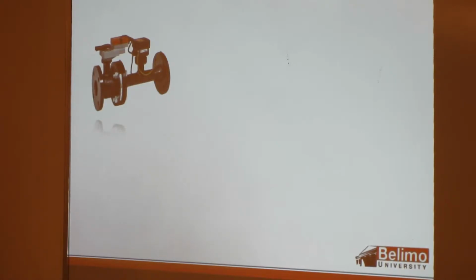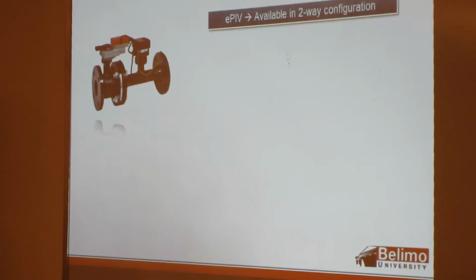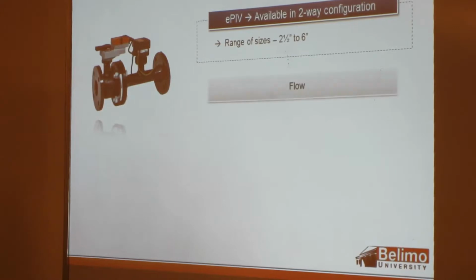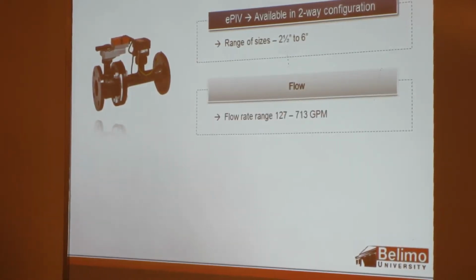Electronic pressure independent valve. We're achieving the same results in a little different manner here. It's available in two-way configuration, just like PICCV. Like I said, all PI valves are going to be two-way. This 2.5 through 6 inch flow rating from 127 to 713 GPM. So that 127, that's the max for say a 2.5 inch valve.